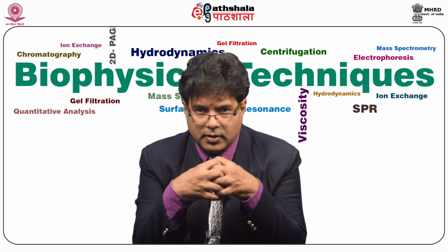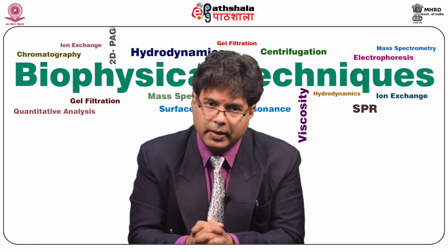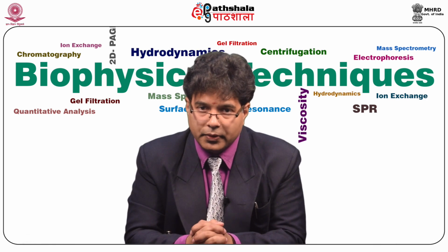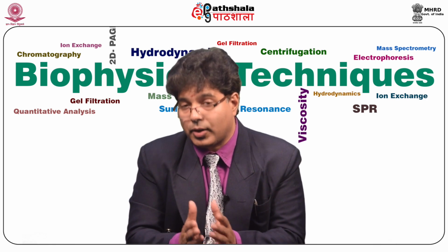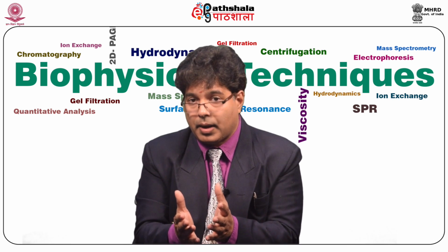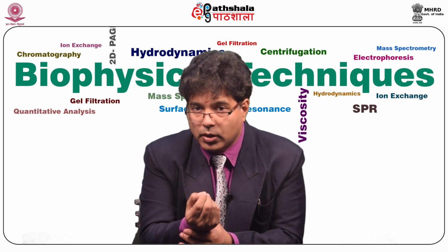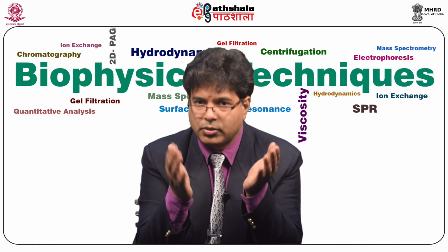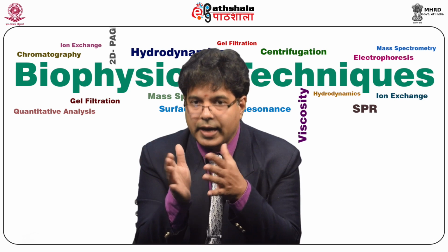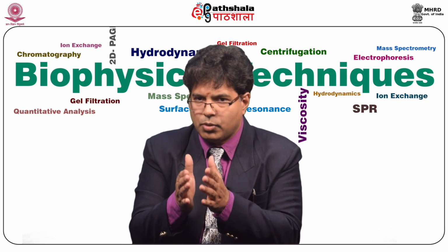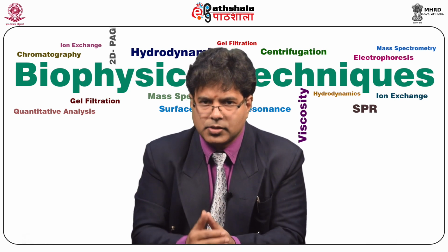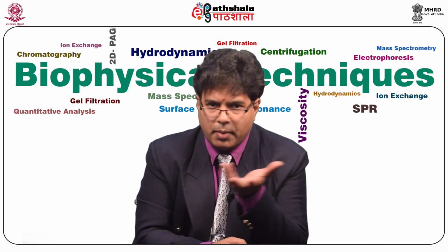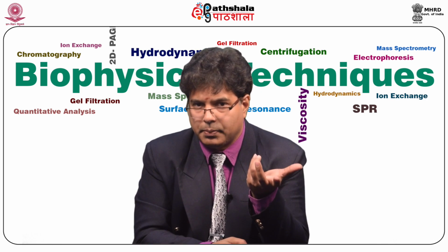Next is mass accuracy. Now, this is a very important aspect which determines, even we have two classes of mass spectrometers, two different classes altogether to do this job. And the instrument which is used to analyze the proteins cannot be as accurate when it comes to small molecular weight quantification experiments. One is qualitative, that is, it is trying to get a very high accuracy in terms of molecular weight, because its mass accuracy is 0.0001 atomic mass unit. Whereas for the quantification purpose, we need only unit mass resolution, where nominal mass plus or minus 0.5 is for analytical purposes.